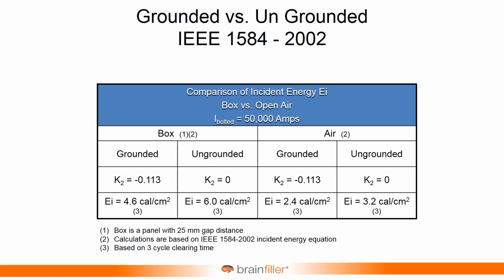I ran a few numbers. This is from the 2002 standard. For example, for a grounded system, you have a coefficient called K2, and that varies depending on whether it's grounded or not. So for the grounded case, for an enclosure, there's 4.6 calories per square centimeter. Whereas if you select ungrounded, there's a different coefficient, K2, it's actually 0. For ungrounded, that number goes up to 6 calories per square centimeter. So there was a difference in the way you handle this. And then for air, there was also a bit of a difference, grounded versus ungrounded.